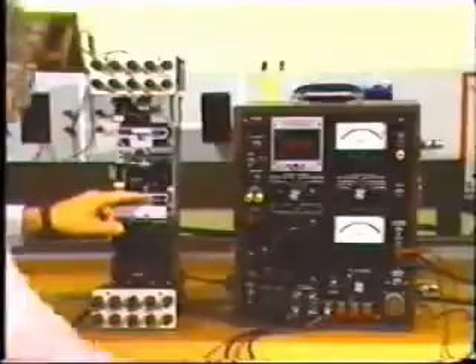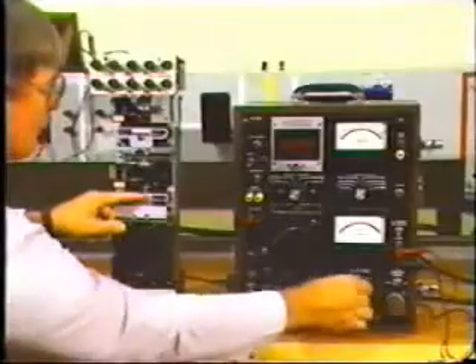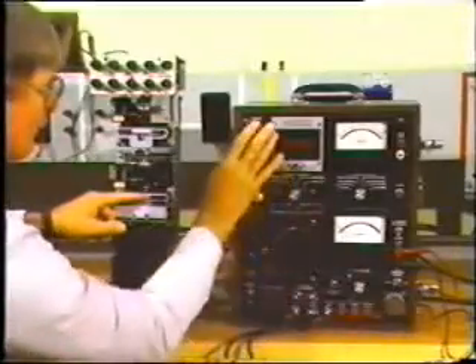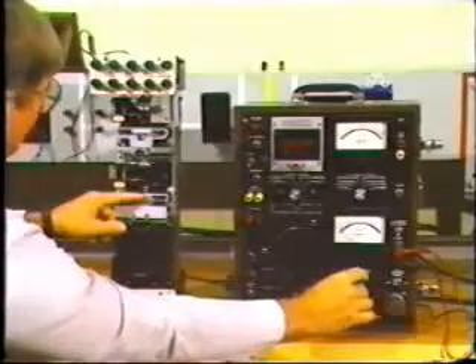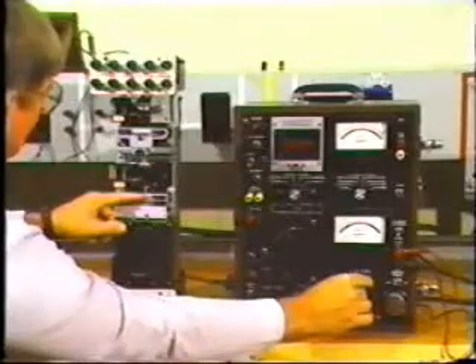When a relay is under test, we need to apply a specific value of voltage or current to simulate signals received under operating conditions. While performing the test, remember that high current or voltage can damage the relay and the test equipment if applied for a lengthy period.